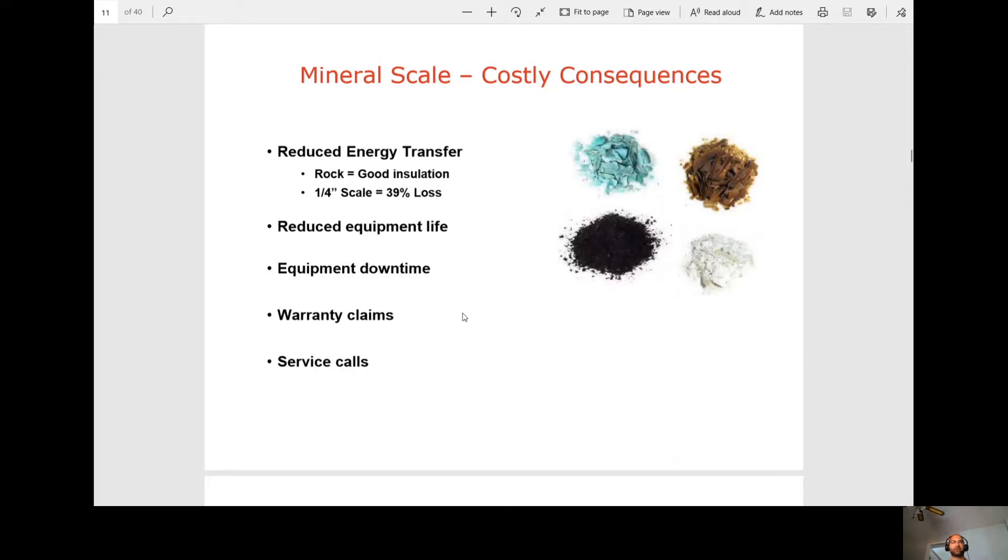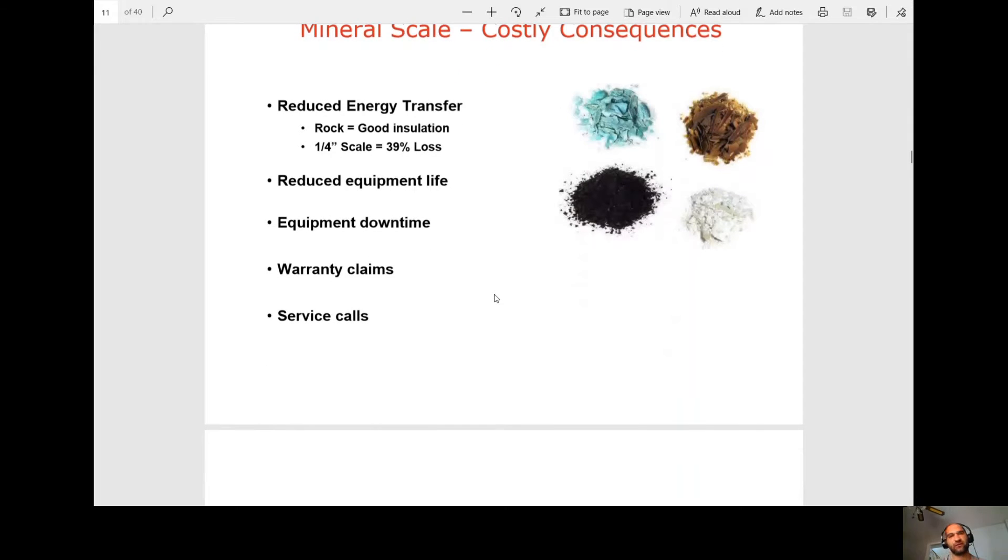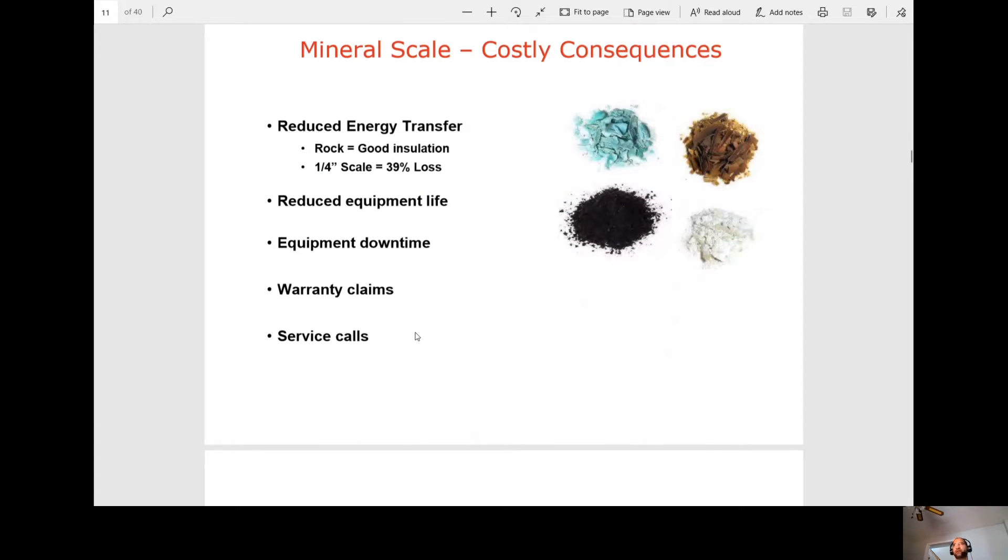So it reduces energy transfer. Rock, so that's like the harder types that we obviously see a lot of here, it acts as an insulator. As we saw earlier, a quarter inch of scale equals 39% loss. It reduces the equipment life. Obviously, the scale is eating away at all the components at the boiler walls. And then that leads to equipment downtime and warranty claims, which if it's scaled up and they haven't been descaling it, the warranty will be voided and it leads to more service calls. So that's why it's important that the customer has a good filtration system and that the boiler is being cleaned out regularly.